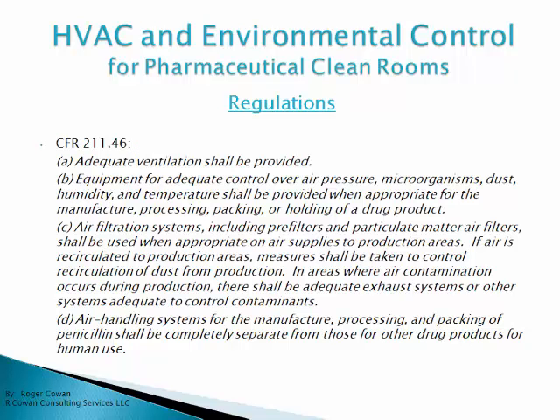There's another GMP reference, CFR 211.46, which states that adequate ventilation shall be provided. Equipment for adequate control over air pressure, microorganisms, dust, humidity and temperature shall be provided when appropriate for the manufacture, processing, packing or holding of a drug product. Air filtration systems, including pre-filters and particulate matter air filters, shall be used when appropriate on air supplies to production areas. If air is recirculated to production areas, measures shall be taken to control recirculation of dust. In areas where air contamination occurs during production, there shall be adequate exhaust systems or other systems adequate to control contaminants.